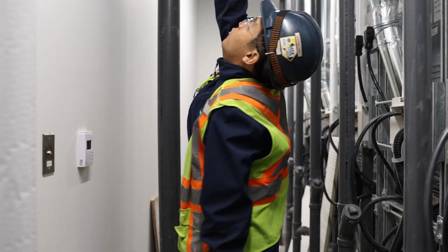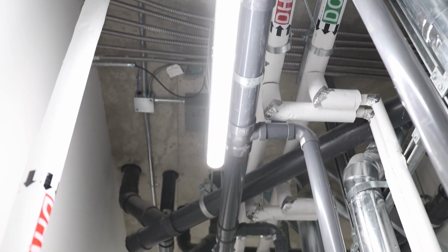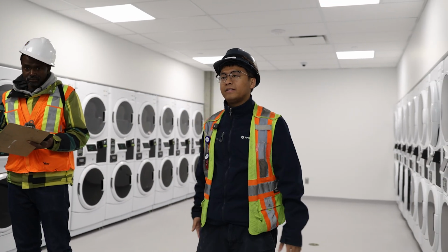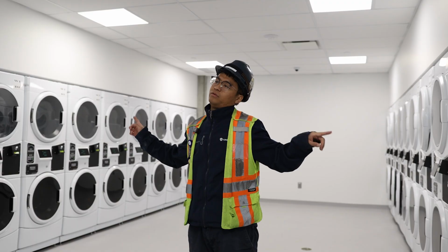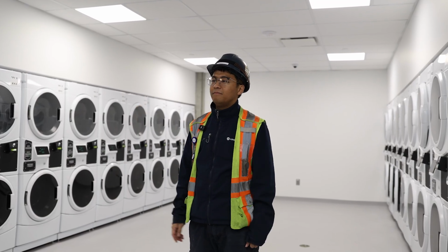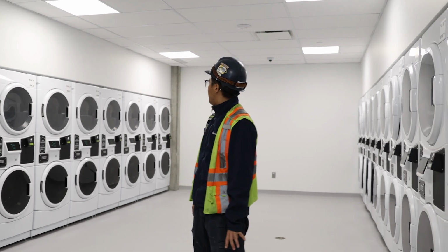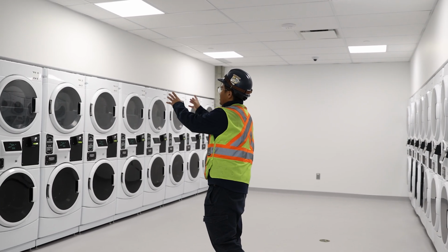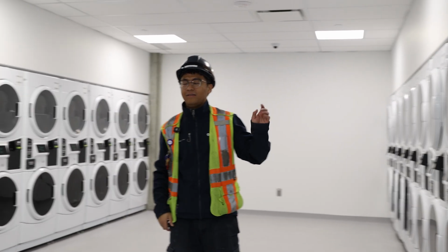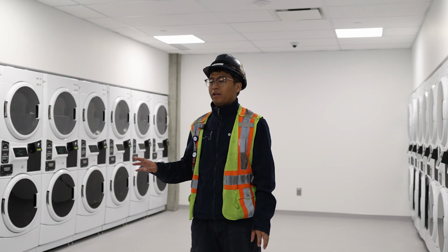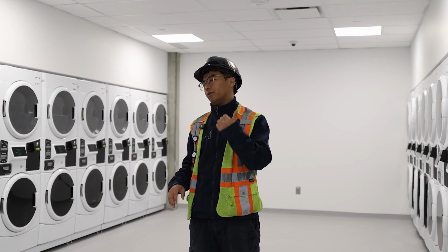If you want, with a display, you can easily tell what the space pressure is. That will be for the space temperature over there and here. The BMS takes the average of those two temperatures, because there are 2 sensors. It's just based on the side: the dryer on this side or the dryer on this side. But if any dryer is running, the makeup air unit will turn on.